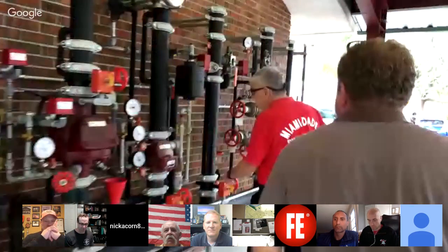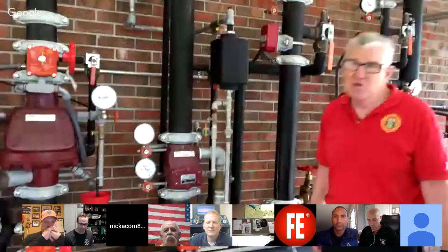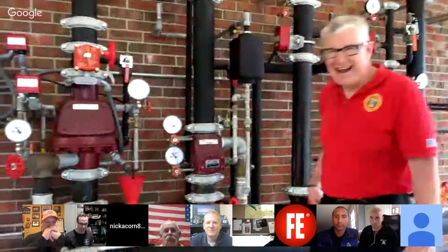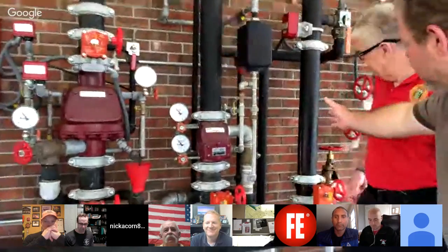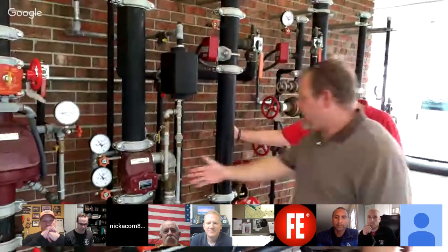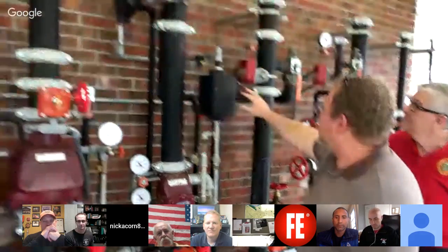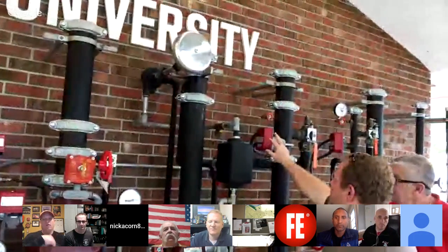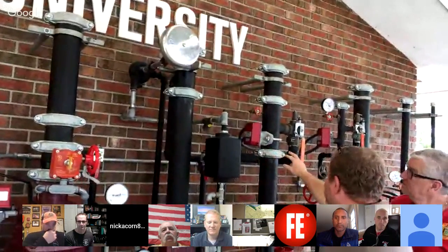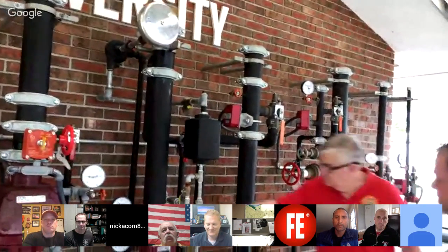Back over here. So essentially, we simulated a sprinkler head going off, right? And that is music to my ears. And then what we would consider, this is our next riser. This is what we would consider like a shotgun riser. It's a newer application. It eliminates the alarm check, right? So we have a retard chamber and a water motor gong. These two devices were replaced by the flow switch. The sole purpose of the flow switch is basically to simulate a sprinkler head going off.